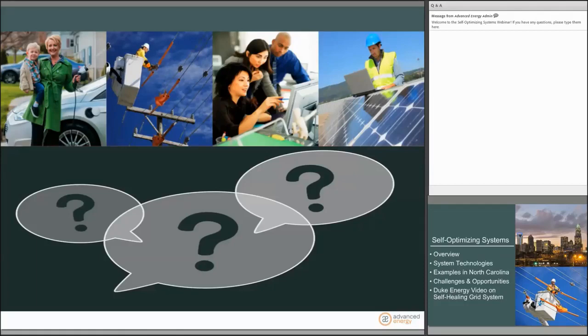That's a great question, Alex. The self-healing and optimizing technology actually enhances response to severe weather events. With the recent experience with Irma in September in Florida, we actually saw self-healing saved over 7 million minutes of customer interruption. One of the benefits with self-healing and reasons that it can enhance restoration is that at winds greater than 35 miles an hour, linemen cannot work on a pole, but you can start doing the remote control with the self-healing. And so the utility is actually able to start restoration earlier than they could have sent crews out in the past. Of course, there's limitations to that. If all the utility equipment is laying on the ground, then the self-healing technology will not help restore power.